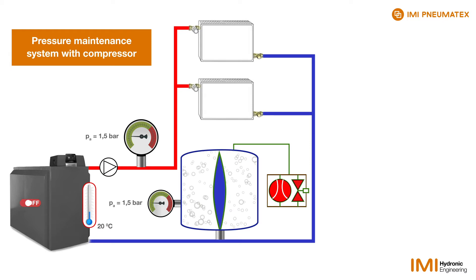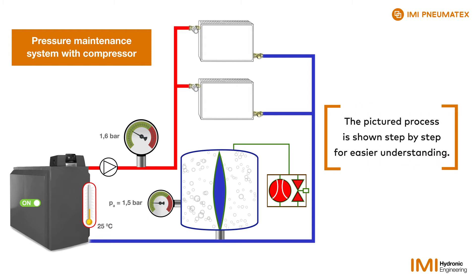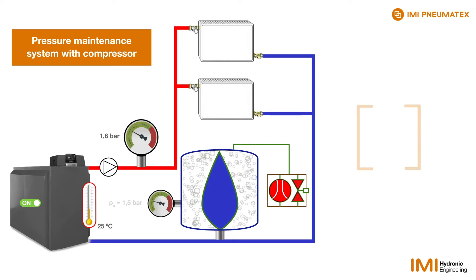If the boiler is now switched on and the water is heated, it expands so that the pressure increases to, for example, 1.6 bar. This pressure forces the water into the vessel and compresses the gas on the other side of the butyl bag to 1.6 bar. If the temperature in the system rises further, the pressure rises to 1.8 bar.